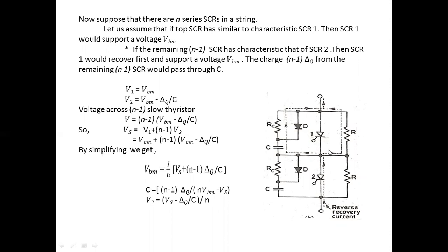The resistance R suffix C bypasses the high currents and protects against high current values. During the charging time of the capacitor C, when forward voltage appears across the diode, it is forward biased, so the diode bypasses the RC during the charging time. This makes the capacitor more effective in voltage equalizing.